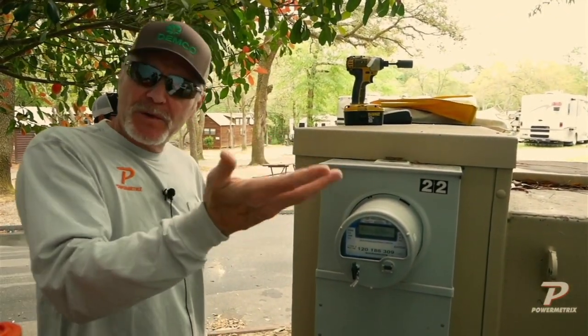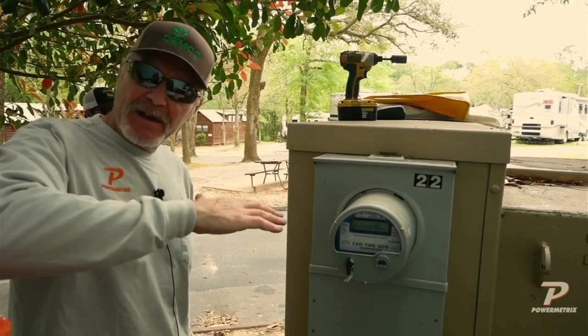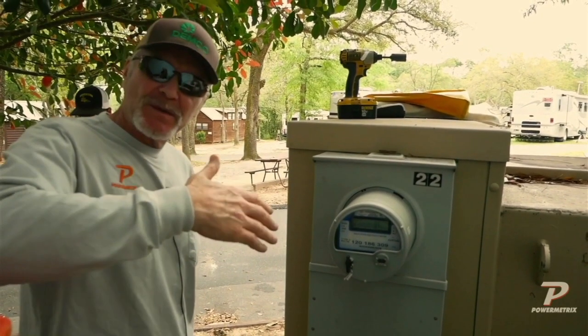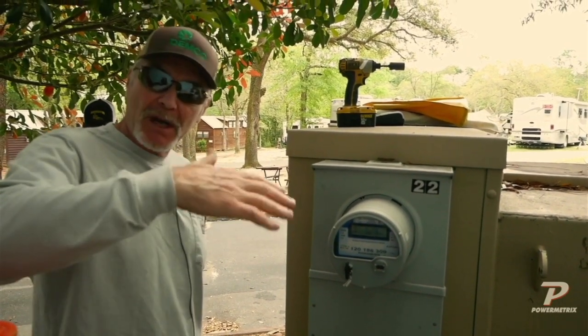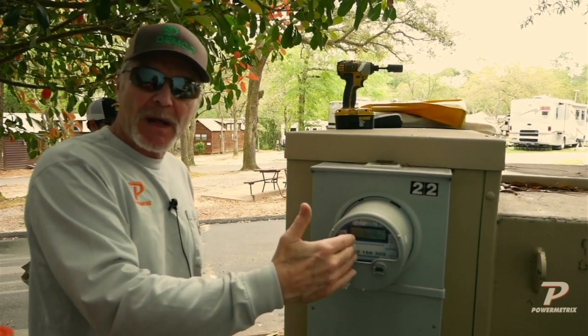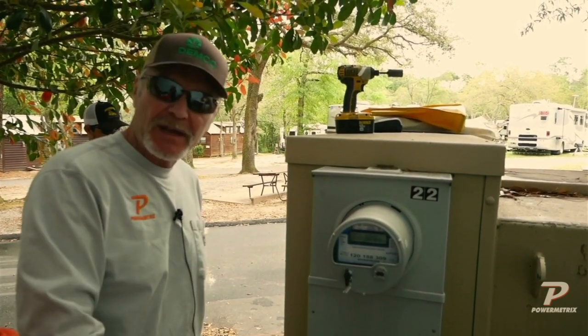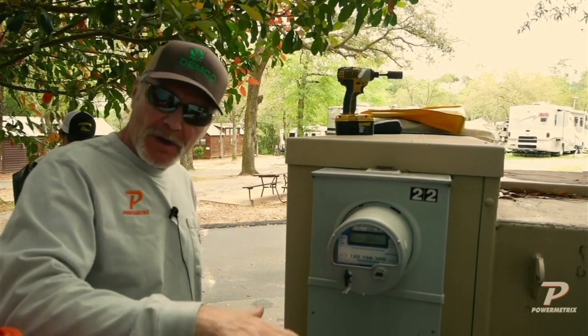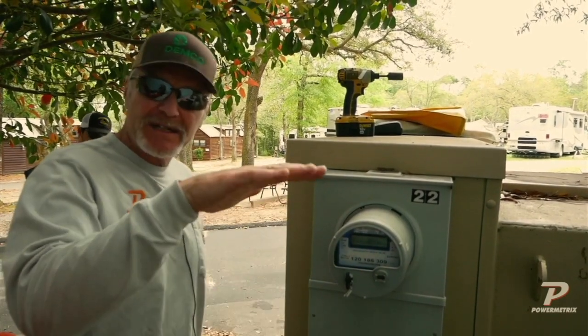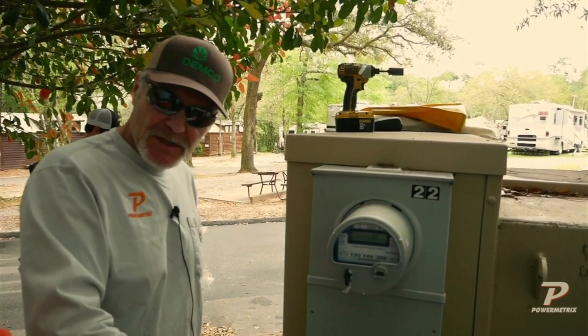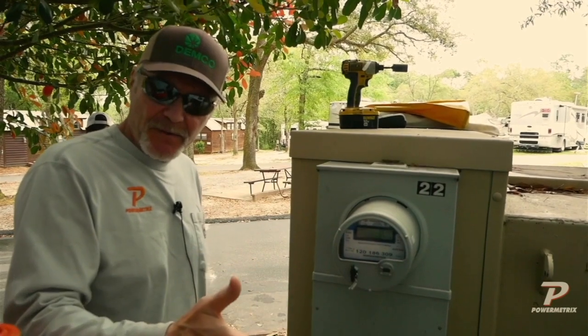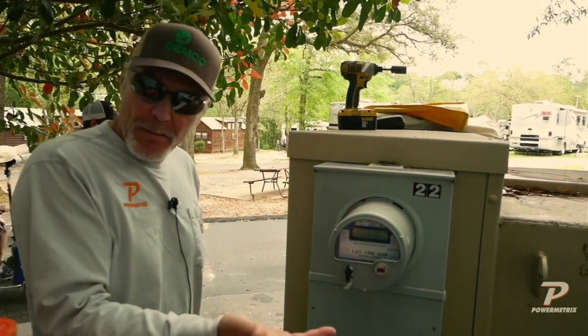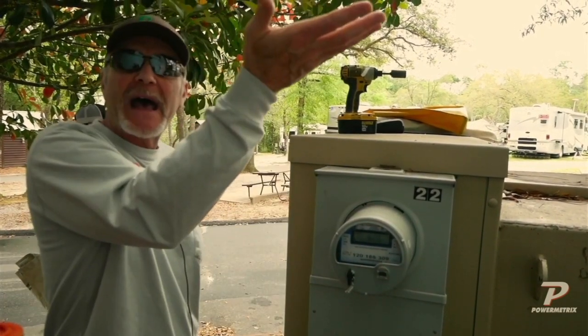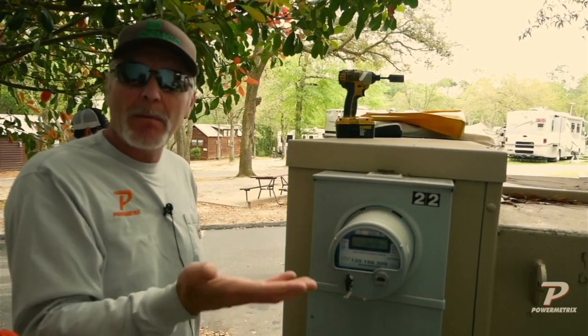Remember, we're doing all of our measurements on the secondary side. So once we do those measurements, to actually bill a customer, you've got to multiply by these multipliers, because we've stepped it down with the transformers. Our step down current or potential transformers step down our currents or voltages to testing levels, which make it safer for us. But when we get ready to bill the customer, we've got to take it back up to actual numbers, and to do that we use these multipliers.